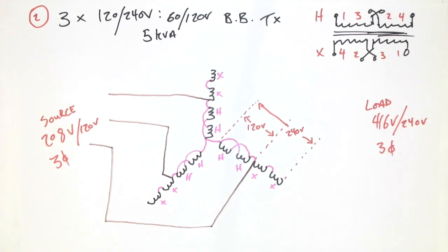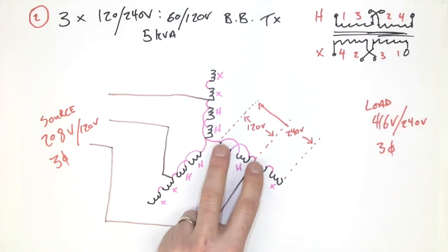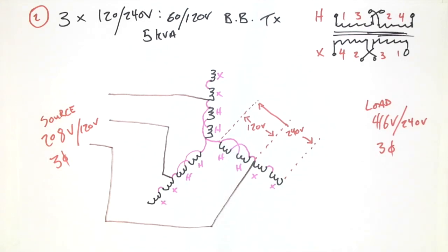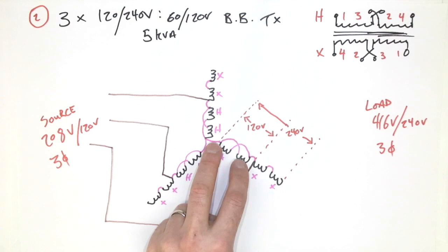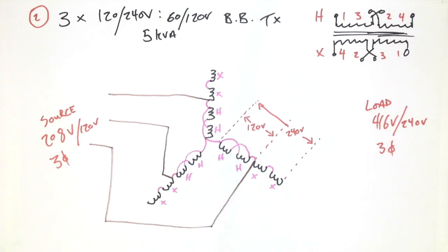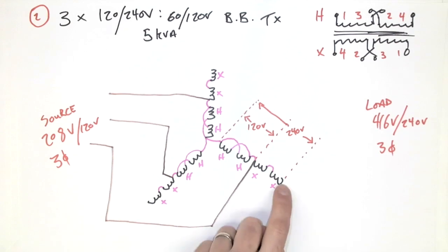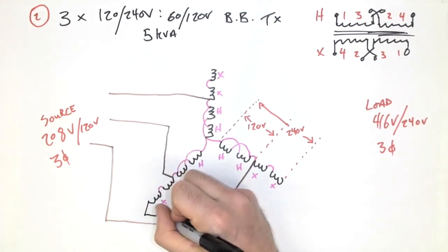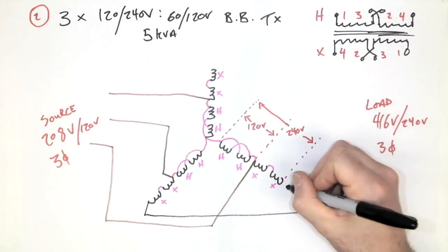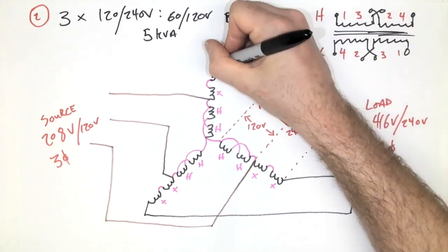Now, how did I know to put the H windings near the middle in order to have that value for my source or my 120 volt phase? Really, it would be up to you. Are you going to put the X windings in the point there at the star, or are you going to put the H windings? It really doesn't matter for this particular connection because they were both 120 here and 120 there. All right, the second connection is going to be to the load, and that is going to require us to connect to the outer reaches of our star-connected auto transformer bank, like this, and like this.